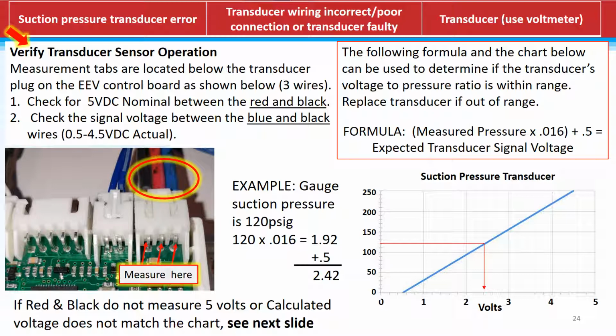In the example on the screen, our gauges are connected and I have 120 psi on the low side. We multiply the gauge reading times 0.016 and we get 1.92. And as you can see in that example, I have to add 0.5 to it. Whatever my calculation, I run first, and then I add that 0.5. My voltage should be 2.42.